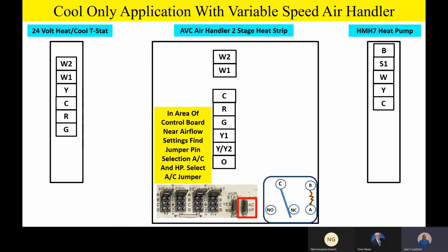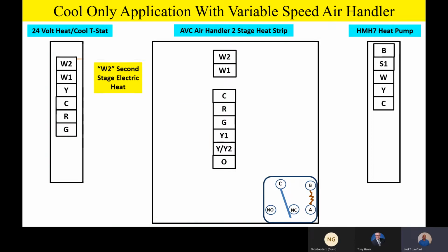Let me say it one more time. When you move that jumper from heat pump to AC on the control board on the variable speed air handler, it's going to ignore the O signal. So now it just thinks it's on an air conditioner outside. Then you're just going to wire it straight through, W2 to W2, W1 to W1. That's our auxiliary heat strip. If you have a 2-stage strip, the thermostat's going to control it all by itself, nothing to do with the outdoor unit.